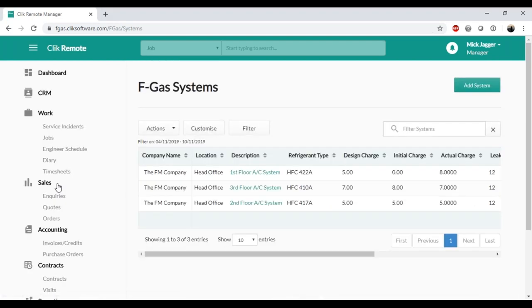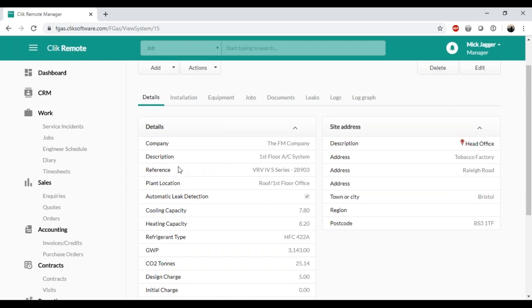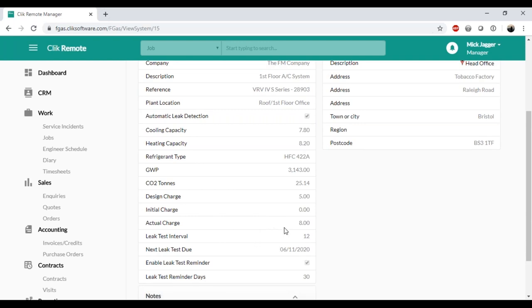If I click on Systems, I'm presented with a list of systems on our database — in this case one company with three separate systems at their head office. Clicking on the first floor AC system shows the company, its location, the refrigerant type the system is running, the initial charge installed, the design charge, and crucially the actual charge at the moment. With the actual charge and refrigerant type, it automatically calculates the GWP — global warming potential — and shows the CO2 tons value. We can also specify when the next leak test is due, the interval, and set reminders.